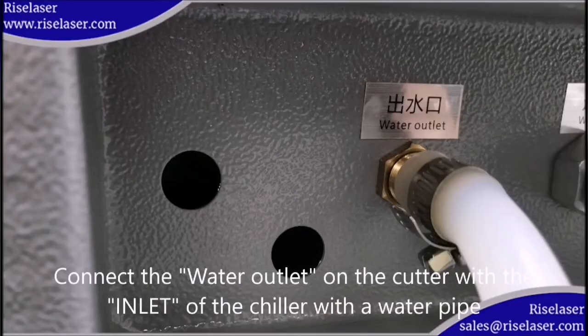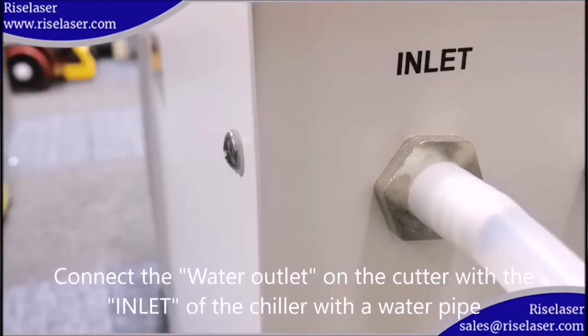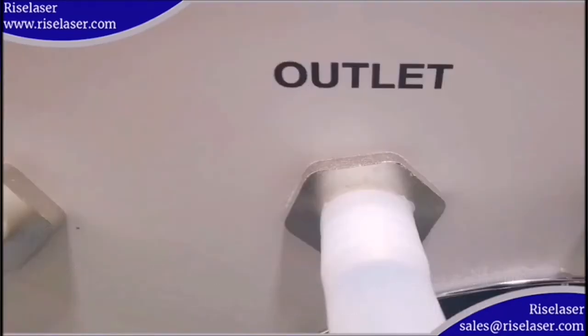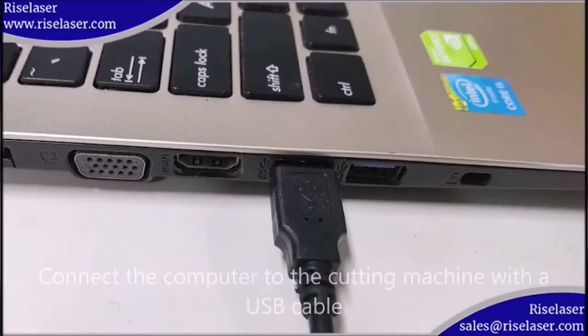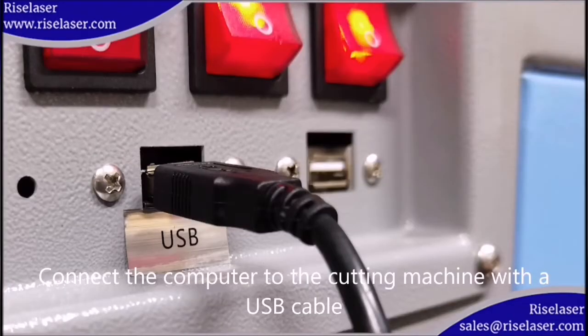Connect the water outlet on the cutter with the inlet of the chiller using the water pipe. Connect the water inlet on the cutter with the outlet of the chiller using the water pipe. Add water here, then connect the computer to the cutting machine with the USB cable.